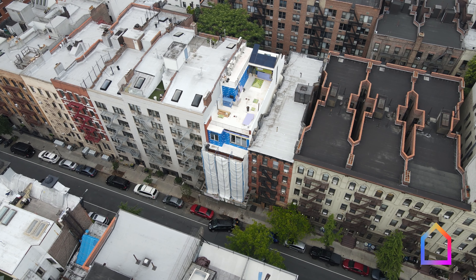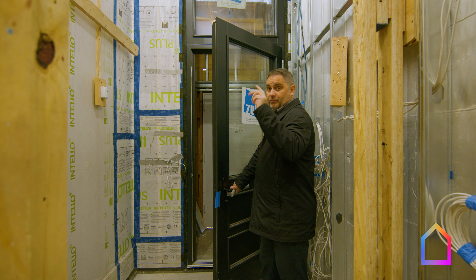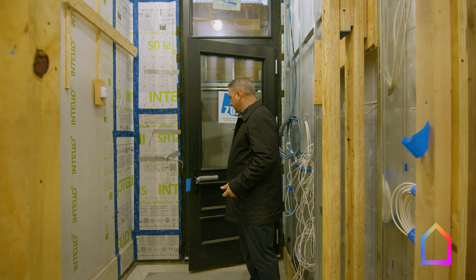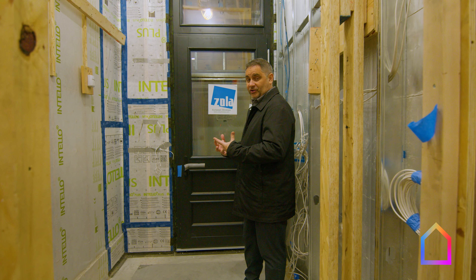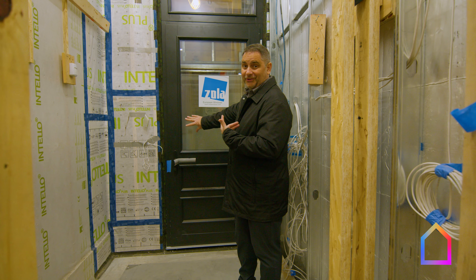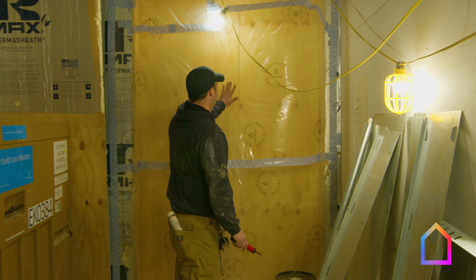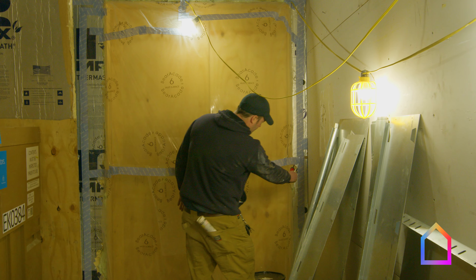The blower door is at the top of the building, seven stories up — one simple blower door test. And you wonder: how can you really pressurize a building like that? It's pressurizing it so much that it sucked this door closed. So it really does work. The blower door does a great job at pressurizing things so you can really find all these holes.